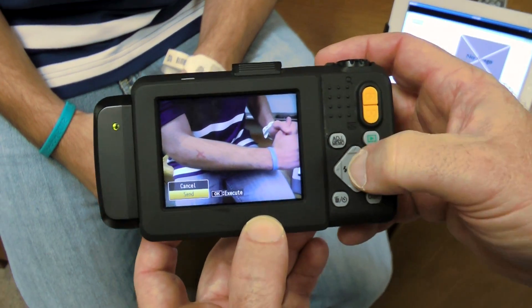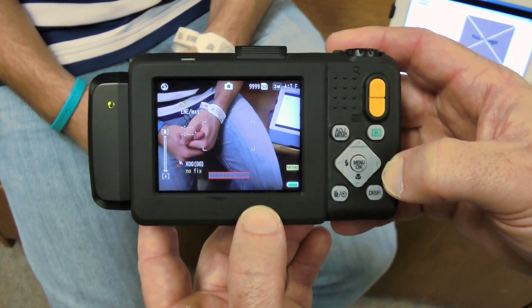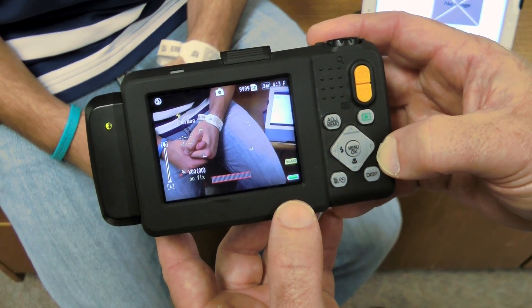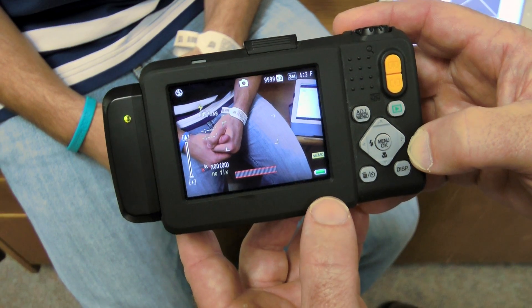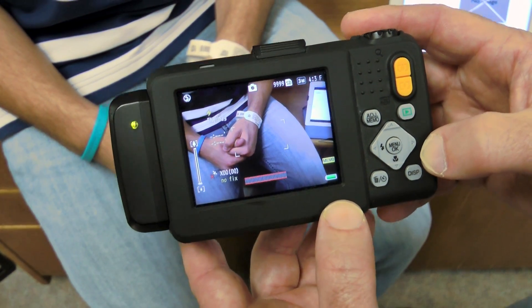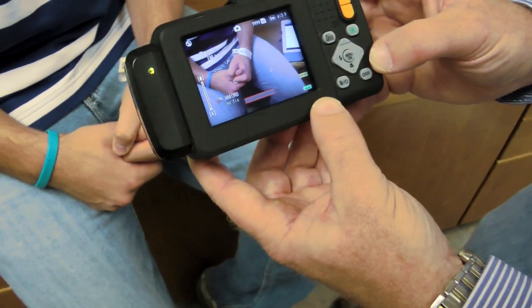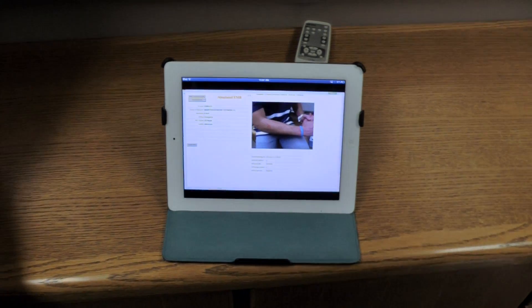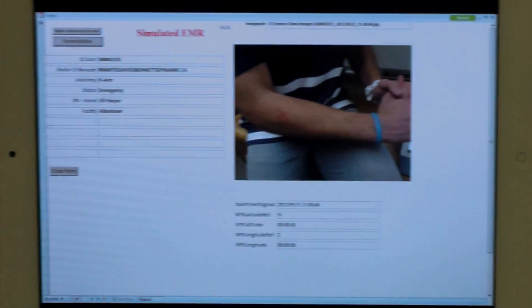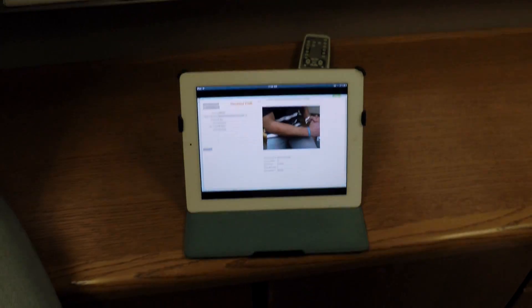We're to this stage — we've reviewed our image, and it has wireless capability. I just press the OK key. It has sent the image, along with the memo data and the ID tag, up into the server. It is then going to match that information with the back-end database or your EMR system. Consequently, one of the advantages is that I will be able to review this information and the images with my patient on this specific encounter. You're simulating that here today with an iPad? I am, exactly. Tablets have become very popular within the healthcare space, so it means it's more portable — I don't have to plug the camera in and tether it or wire it to the PC. Everything happens seamlessly within the server.